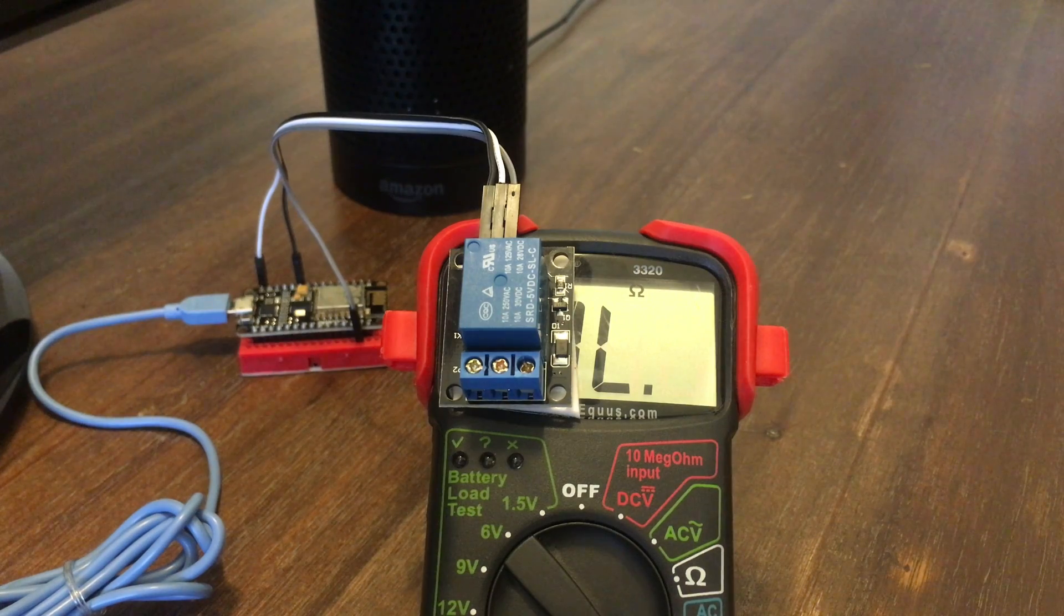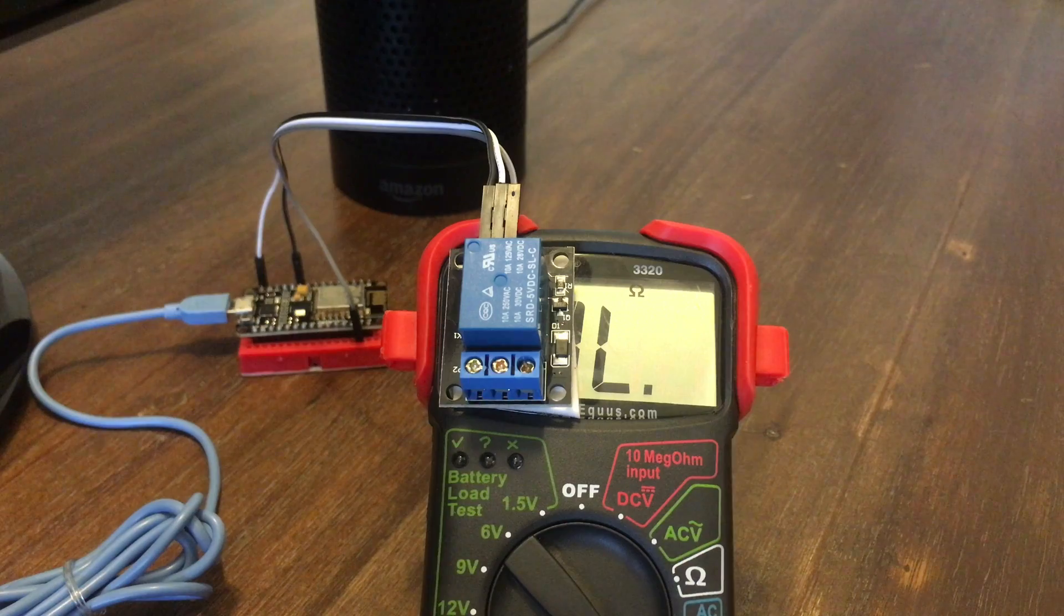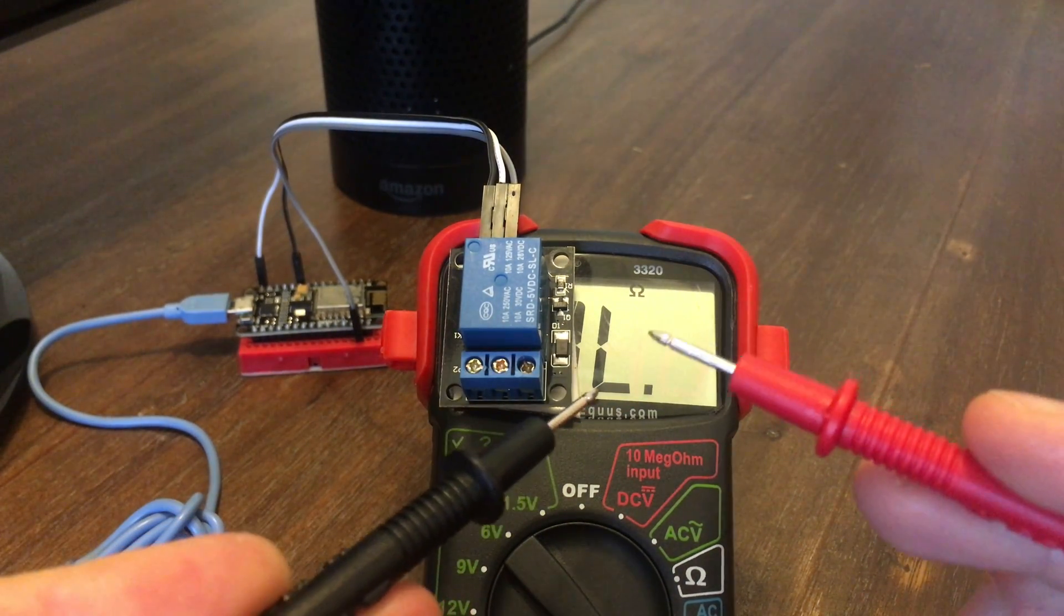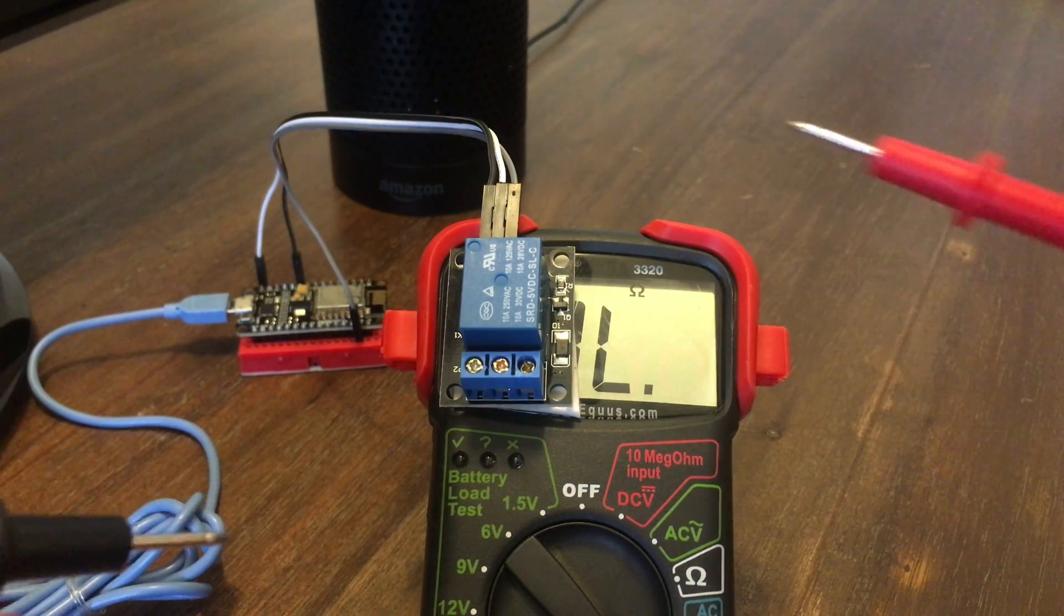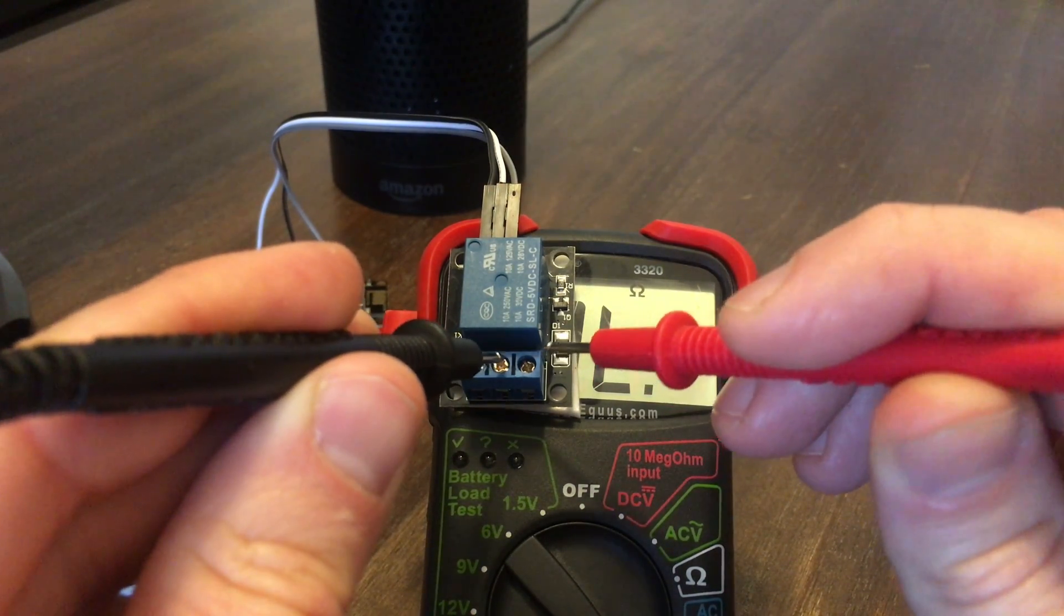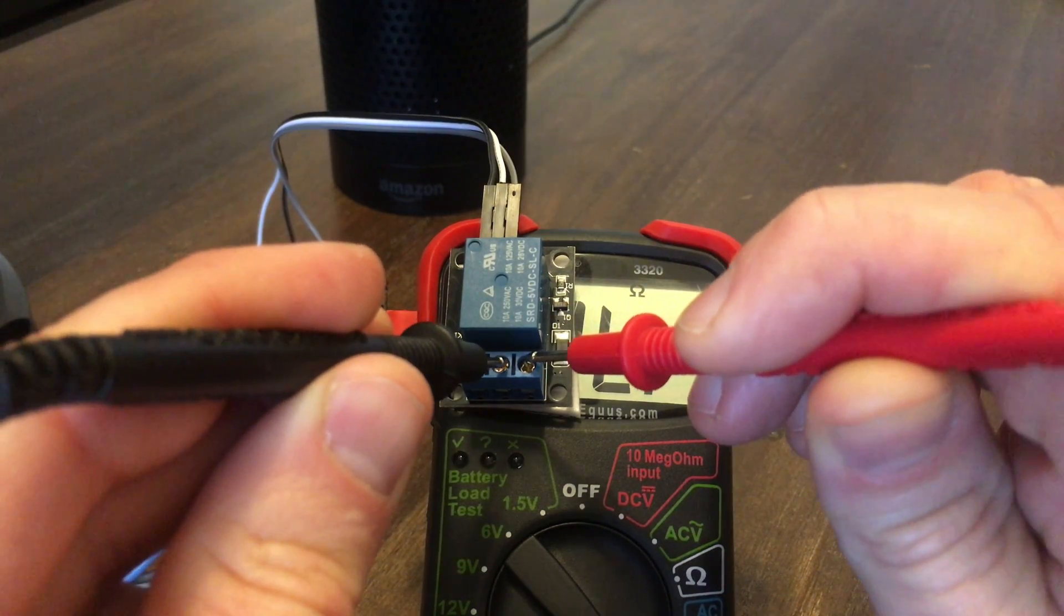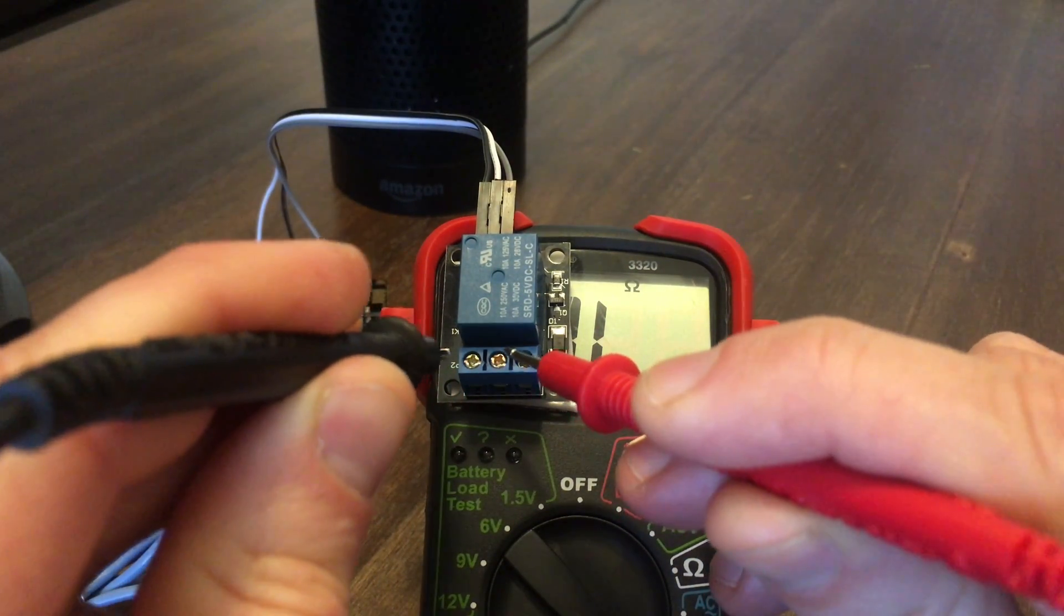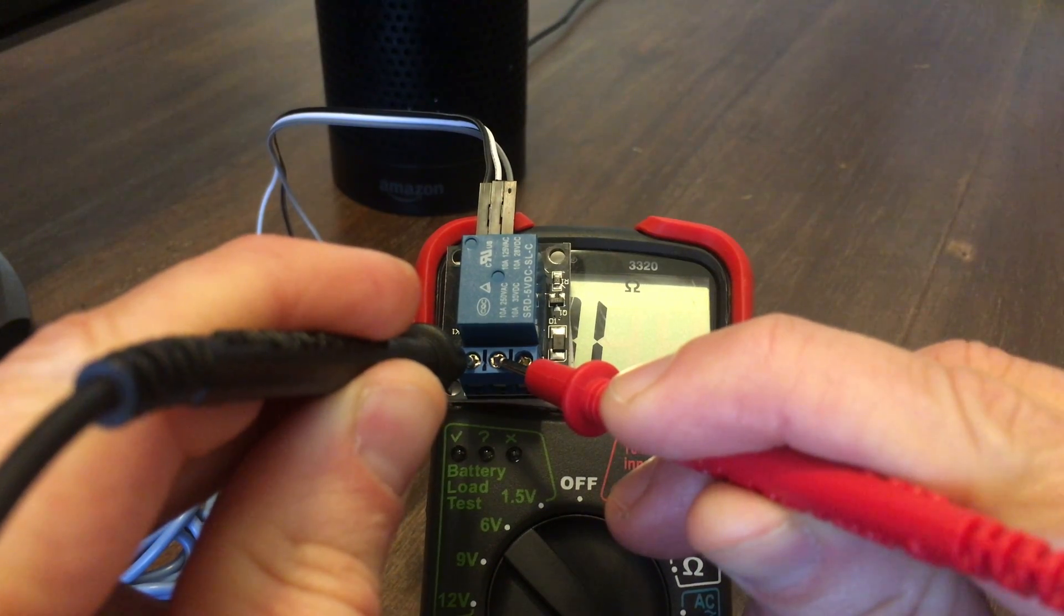Before we install this, let's make sure we know which contacts on the relay are open or closed when we turn it off or on. Get your multimeter and put it in continuity mode. So when we have a closed contact, it beeps like this. On this relay, these two contacts are closed when the relay is off. These two contacts are closed when the relay is on. So it should not beep now because it's currently off.